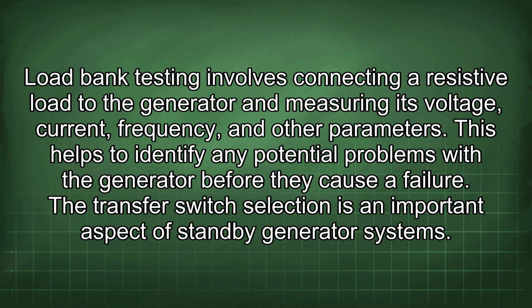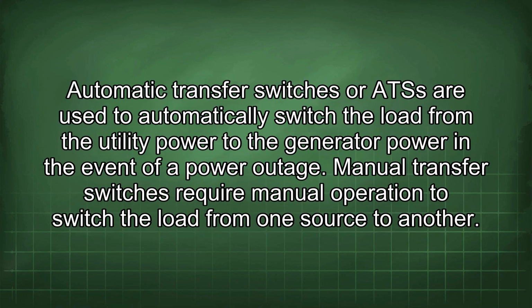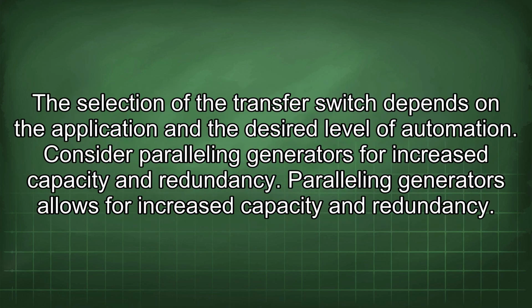The transfer switch selection is an important aspect of standby generator systems. Automatic transfer switches, or ATS, are used to automatically switch the load from the utility power to the generator power in the event of a power outage. Manual transfer switches require manual operation to switch the load from one source to another. The selection of the transfer switch depends on the application and the desired level of automation.